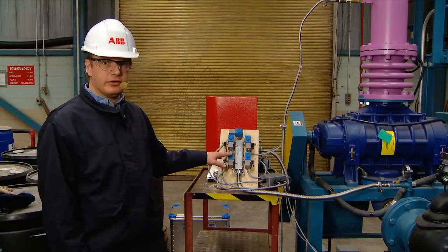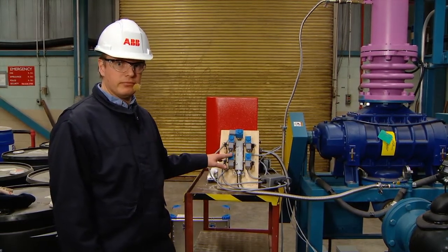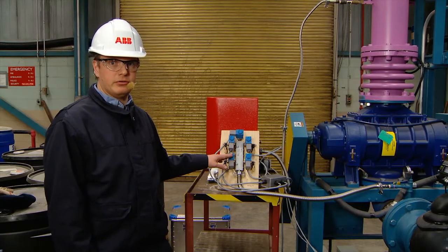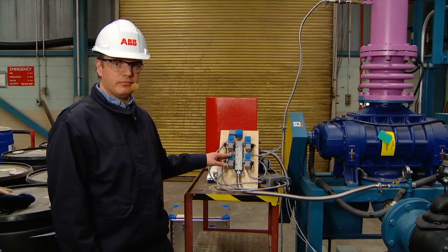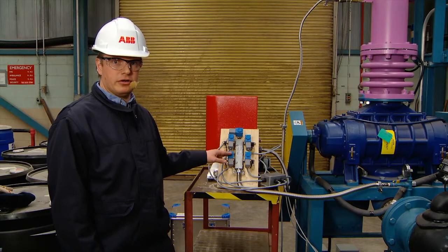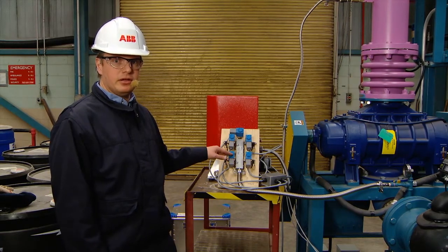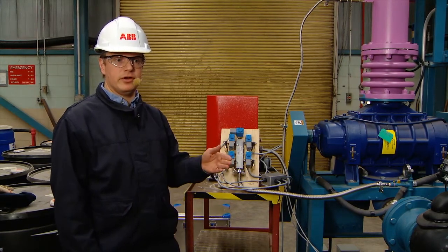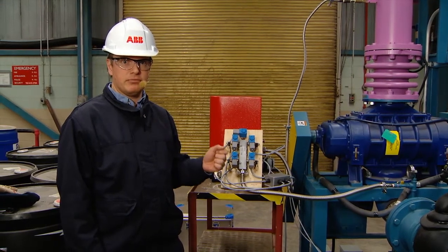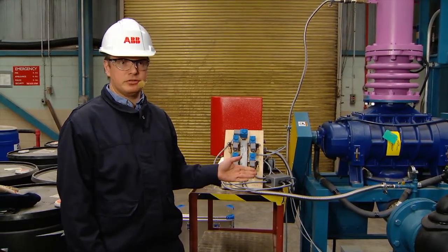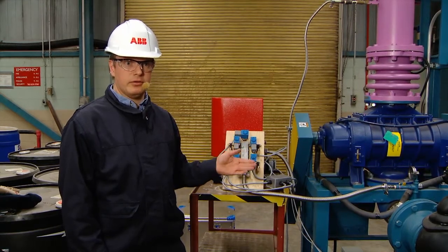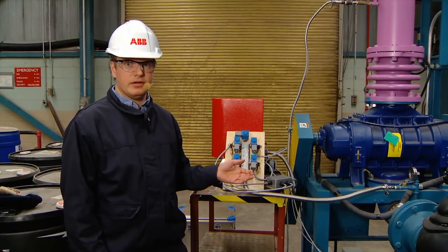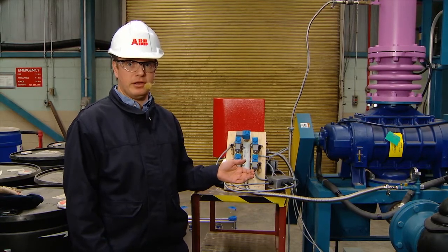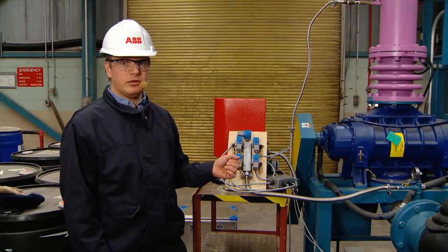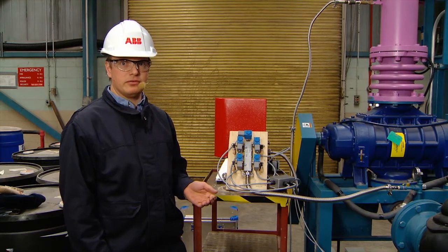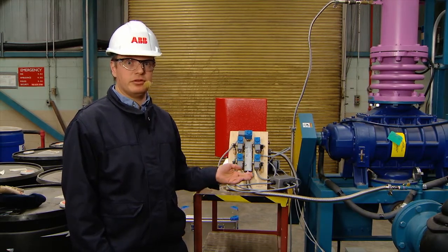Each valve is then individually controlled from the control system and opens in a sequence that is predetermined by the program. Each valve has a certain leakage rate. This leakage rate is generating a leakage to the vacuum pumps. By this vacuum pump leakage and the final pressure, we can determine the pump capacity. This pump capacity is then a basis for the pressure readings used for the VZ406, which is in the next stage measuring the water extraction rate.